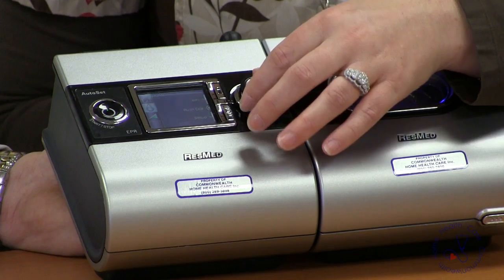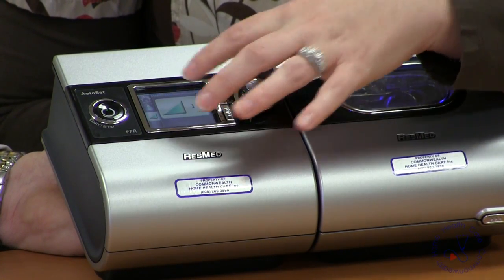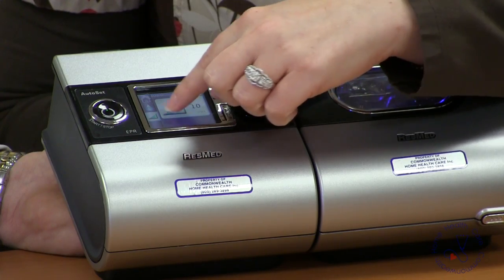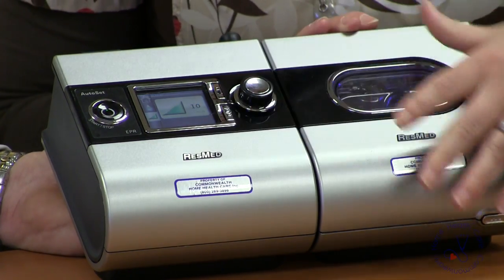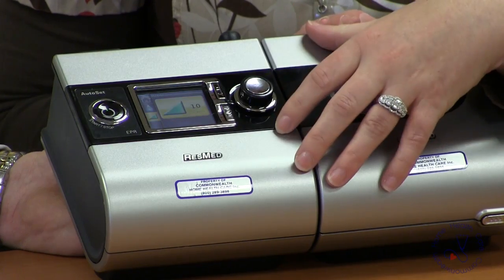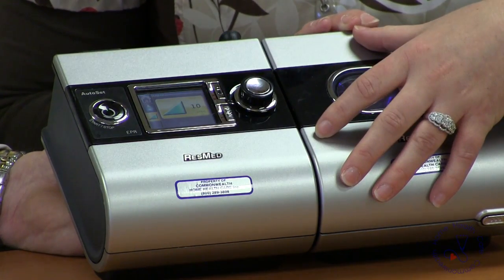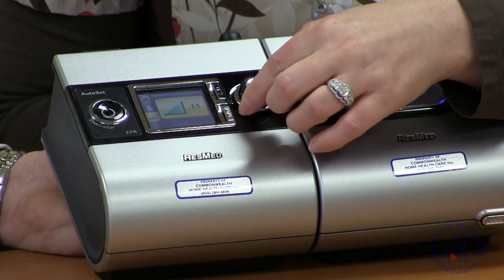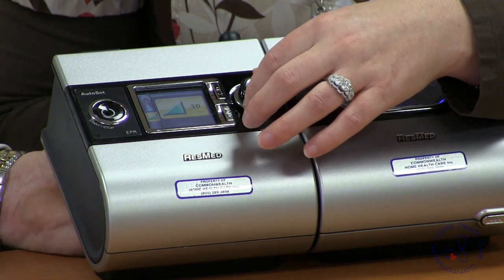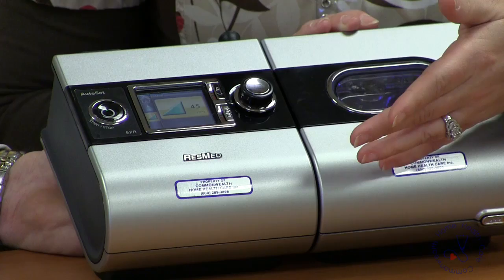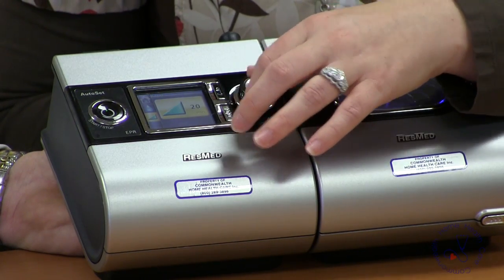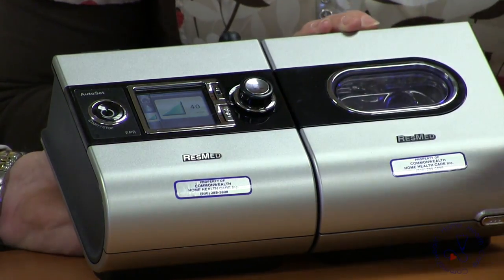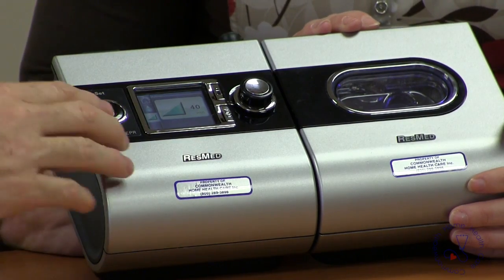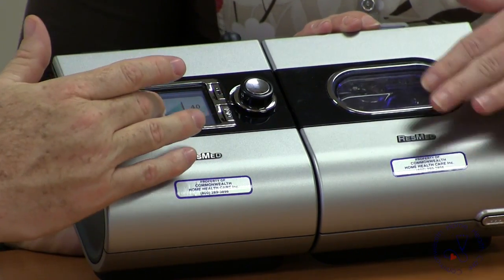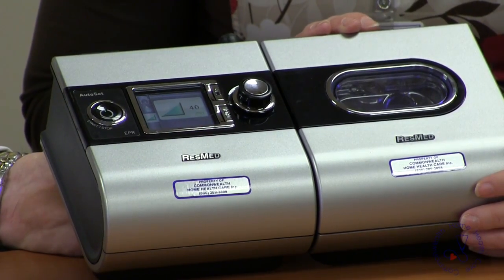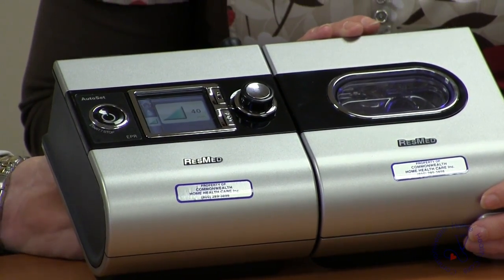Yes, you would just take the dial, scroll down until the ramp is highlighted, looks like a little triangle. Right now it's set at 10 minutes. We would press the button down, the screen lights up yellow, we know we're able to make our change, turn the knob, and it goes up by 5-minute increments. You can go up to 45 minutes or as low as 5. So you just press it. There you go, and it's locked in. And that locks it in. And so it'll start at the lowest pressure, and over a period of 40 minutes, it takes me up to my prescribed pressure. Yes. Okay, great.